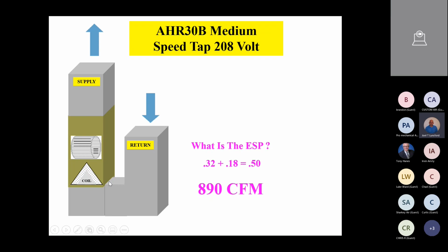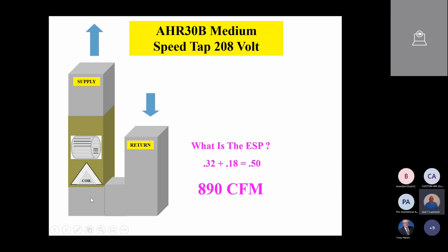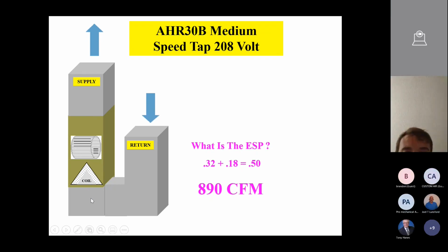Look at my cursor. Let's say my filter is right here at the edge of the cabinet. I'm going to come over here and poke a hole in the cabinet below the coil, so I can actually read that static pressure where it's sucking against that filter as well. Does that make sense? Now that makes sense.